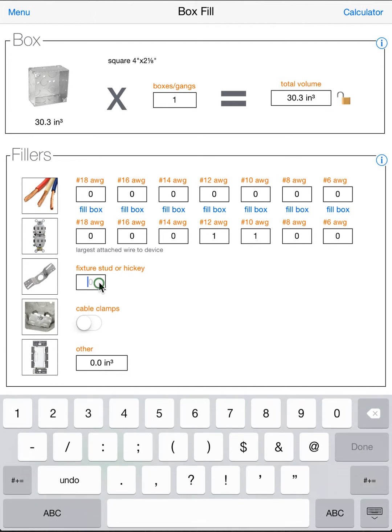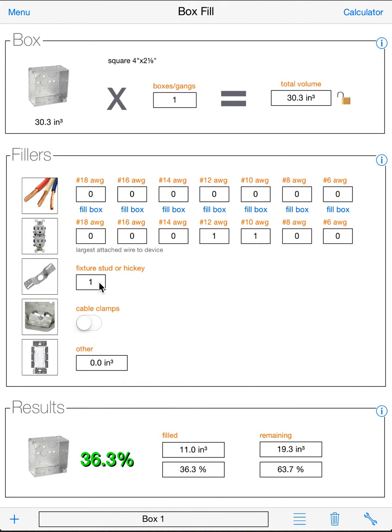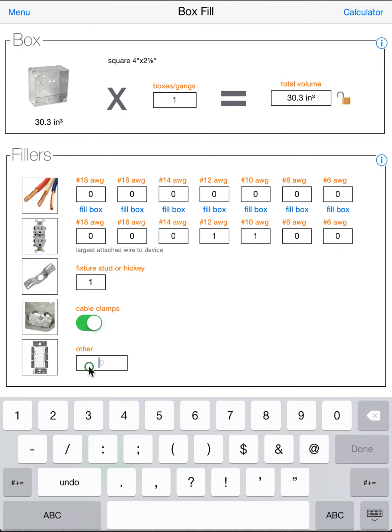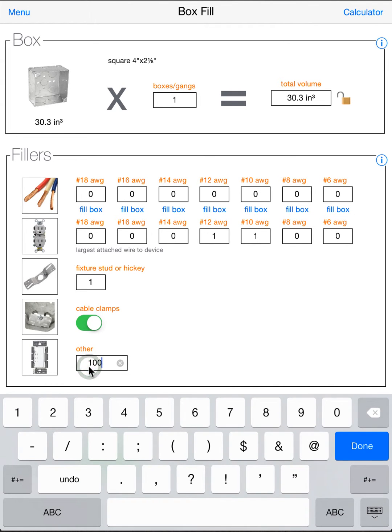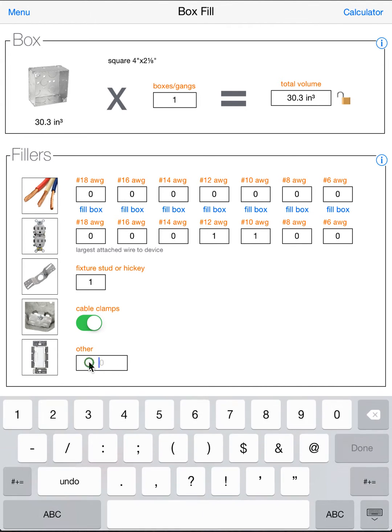A fixture stud or hickey. If you have a fixture stud or any kind of hickey in the box that you're mounting a light to or a fixture to, you can add that in. If you have internal cable clamps in the box, you're going to want to turn this switch on. That'll add fill as well. And other is a spot where you can put devices that don't fall into any of the other categories. Maybe a dimmer, motor control, timer, something like that. And that box you can just type in. So you can type in your 100 cubic inch or whatever you want.